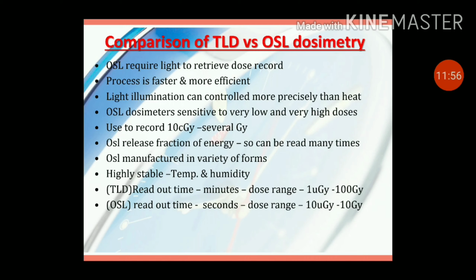several sievert. Most of the energy stored in TLD is depleted upon heating, leaving no possibility to reread the material. But in the case of OSLD, they release only a fraction of the absorbed energy when optically stimulated. So OSLD dosimeters can be read a number of times, which can reduce the uncertainty of a result.